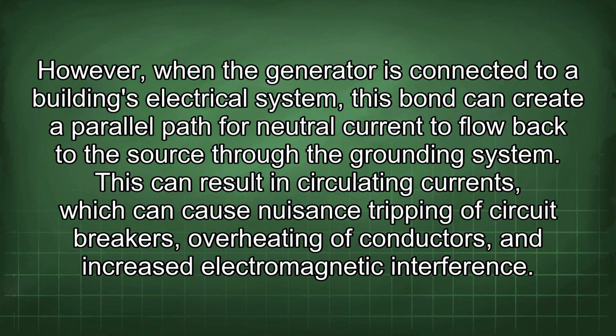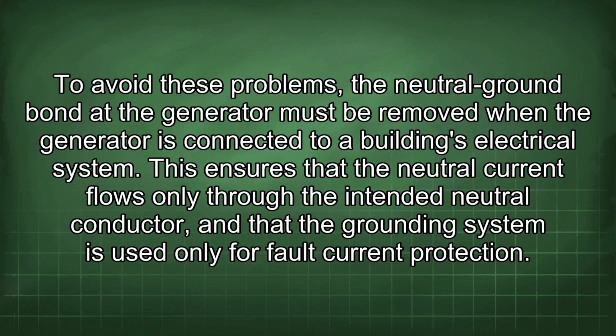This can result in circulating currents, which can cause nuisance tripping of circuit breakers, overheating of conductors, and increased electromagnetic interference. To avoid these problems, the neutral ground bond at the generator must be removed when the generator is connected to a building's electrical system. This ensures that the neutral current flows only through the intended neutral conductor, and that the grounding system is used only for fault current protection.